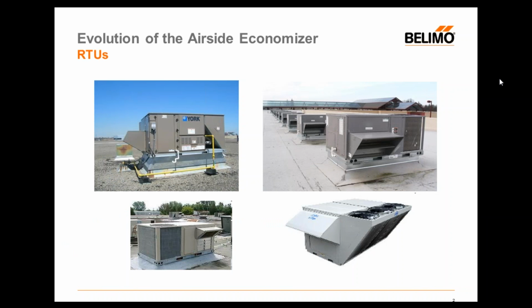For this presentation, I'd like to focus on packaged rooftop units. The use of economizers and their controls has steadily increased with the growth of the RTU market. RTUs are used in 60% of buildings. Currently, approximately 700,000 RTUs are produced annually for new construction and replacement. Over the years, RTU physical appearances and sizes have changed due to the many DOE energy efficiency program updates. You can see on the screen some current RTUs, and you can see the hood where the economizer would be located.